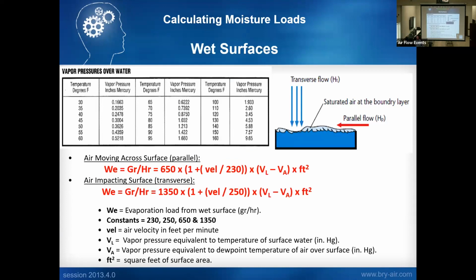Wet surfaces, again, these are more found in water treatment plants, but they're basically open tanks of some kind of fluid that would add moisture. Some of the critical things to deal with when you're looking at wet surfaces, number one is how the air is hitting that tank. Is the air perpendicular to the tank? Is it parallel to the tank? That's going to affect how much moisture is picked up.